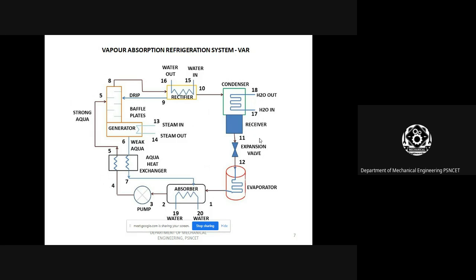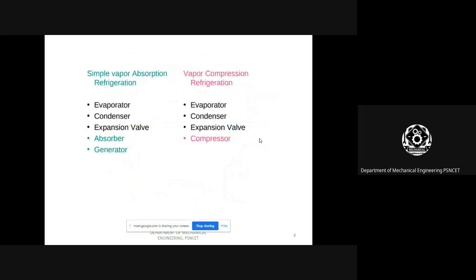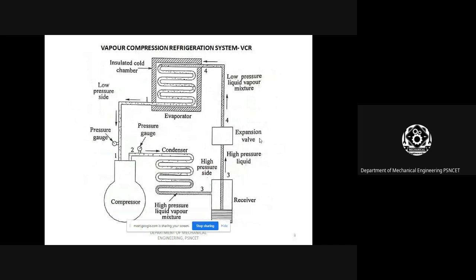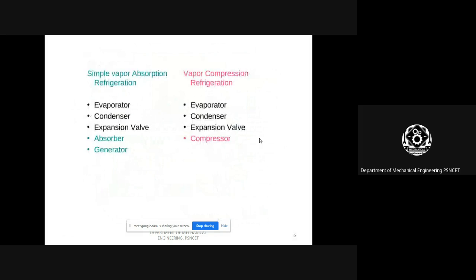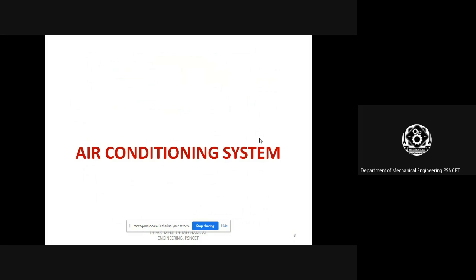So there are two systems: the vapor compression refrigeration system, and another one, the vapor absorption refrigeration system, VCR and VAR. The main difference between VCR and VAR is that the compressor is replaced by the absorber and generator. Here heat is supplied, while there a mechanical device is used just to increase the pressure and temperature. That's it. Right, now we go to the air conditioning system.